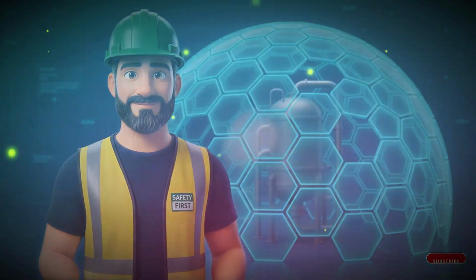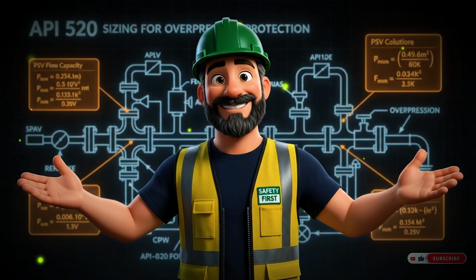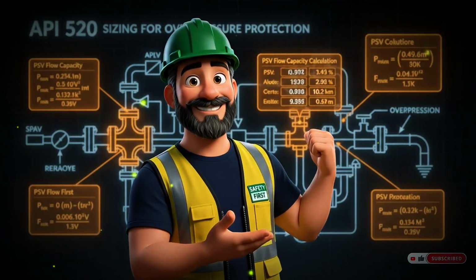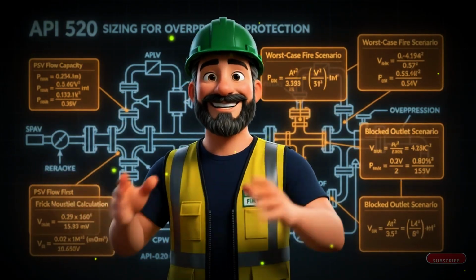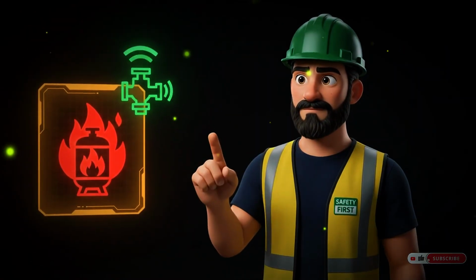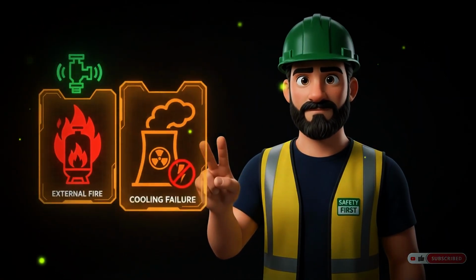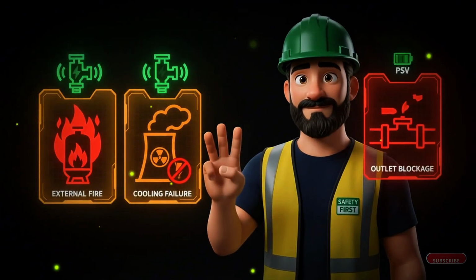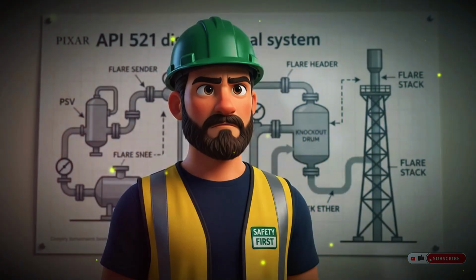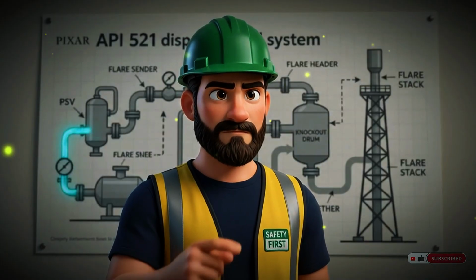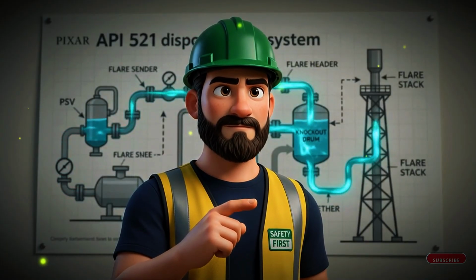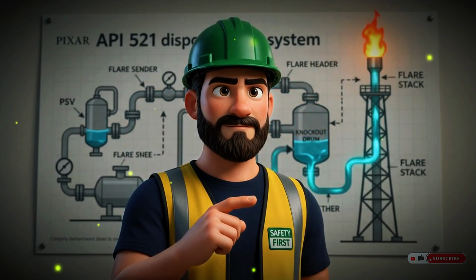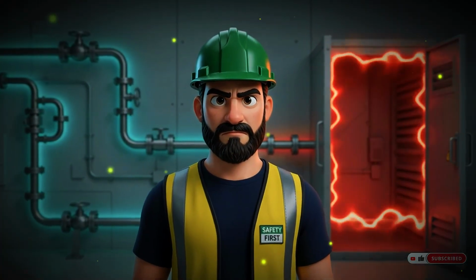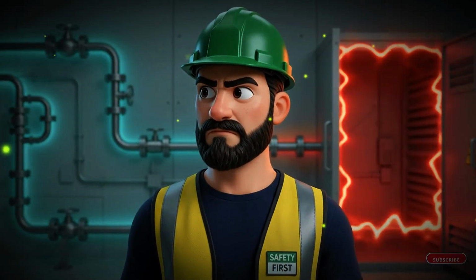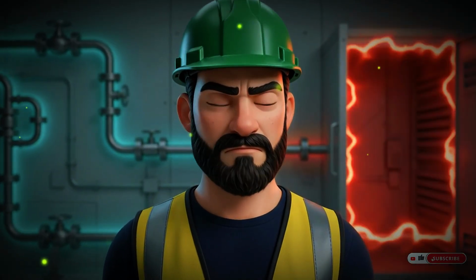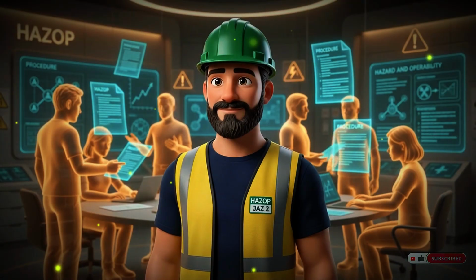API 520 and API 521 protect the system against the worst-case scenario, overpressure. API 520 defines how to size pressure relief valves for every possible overpressure scenario: external fire, cooling failure, accidental outlet blockage. API 521 defines what to do with the fluids released by those valves, how to design the flare system, how to ensure that flammable vapors are not discharged at ground level. In Texas City, the failure to comply with the intent of these standards was directly responsible for the creation of the explosive cloud that killed 15 people.